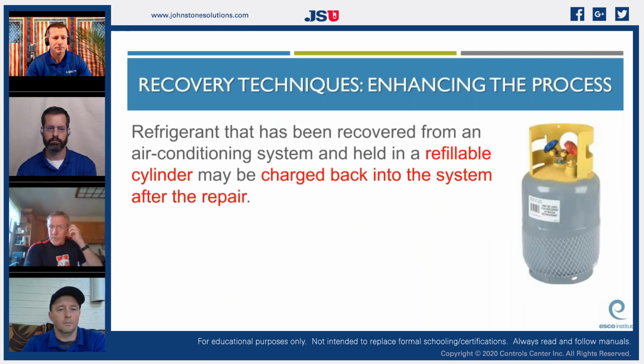Refrigerant that has been recovered from an air conditioning system and held in a refillable cylinder may be charged back into the system after the repair. Another practice we did, and not to just drag on about this, is that all our techs carried a clean 10-pound cylinder in their truck. We had a 50-pound R22 and a 50-pound 410A in the service vans, but we also had a 10-pound that they offloaded and pulled a vacuum on, so that when they were working on a system they could put the refrigerant into it. It held almost all residential charges back then. Then they could do the repair, evacuate, and put the refrigerant back in that the homeowner had already paid for when they bought the system. You betcha. Especially as refrigerant got more expensive.